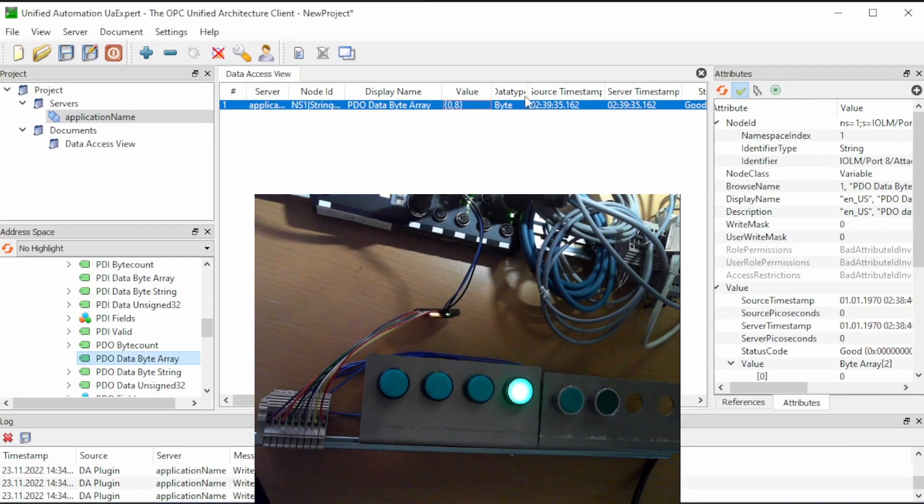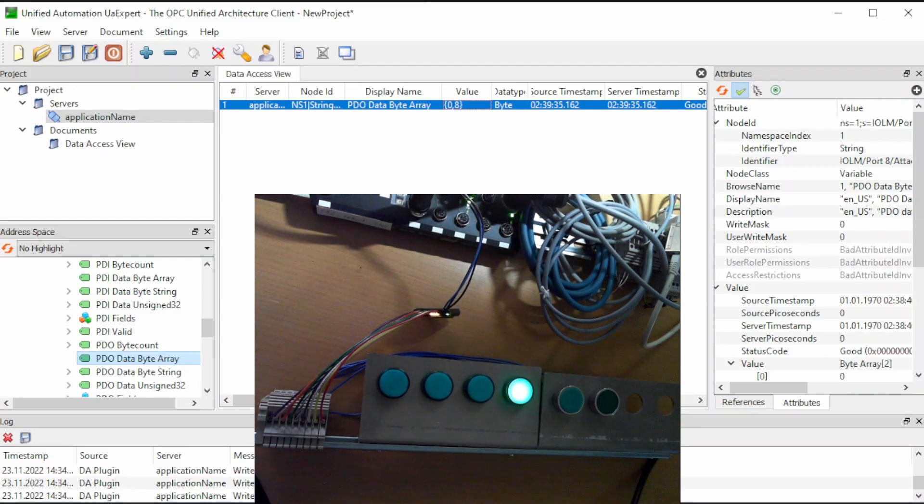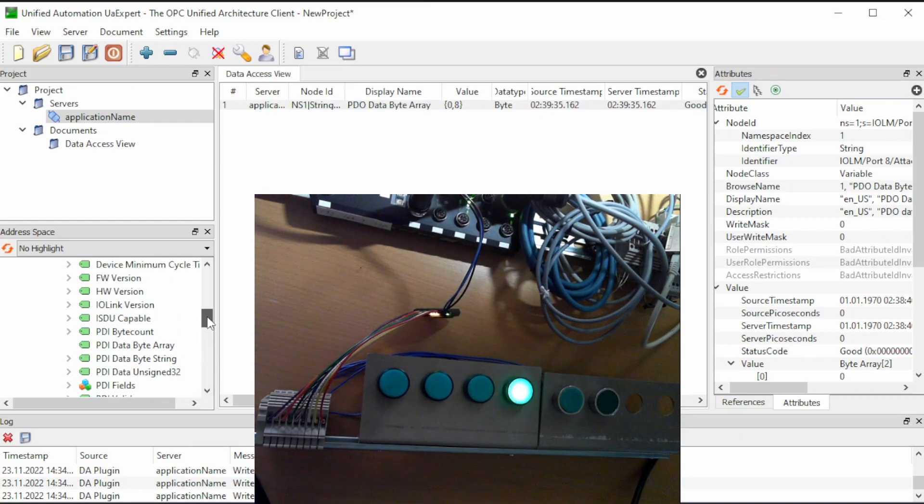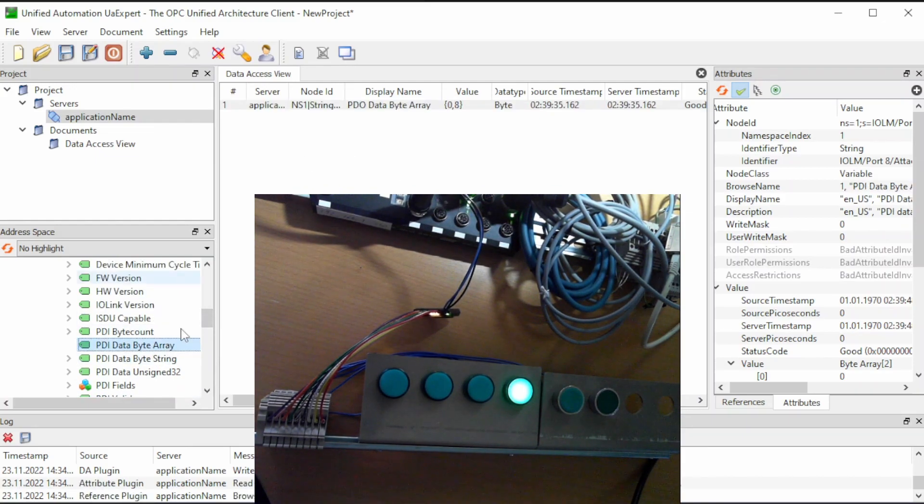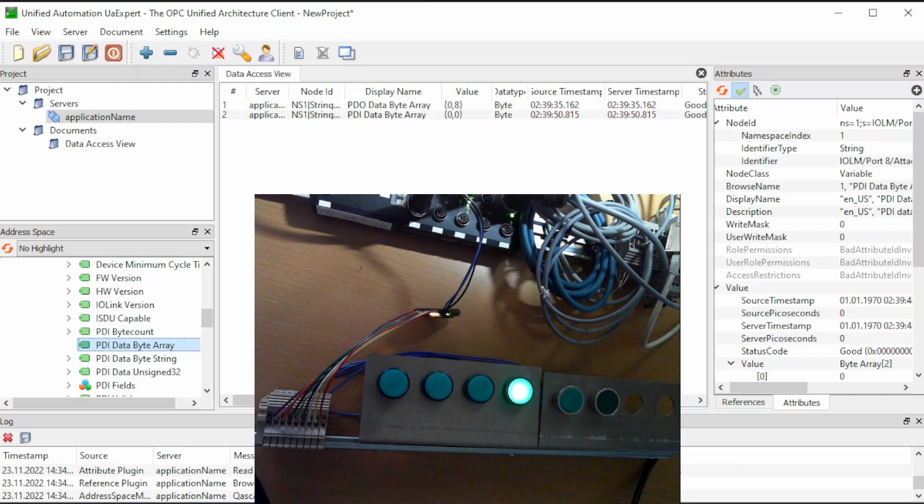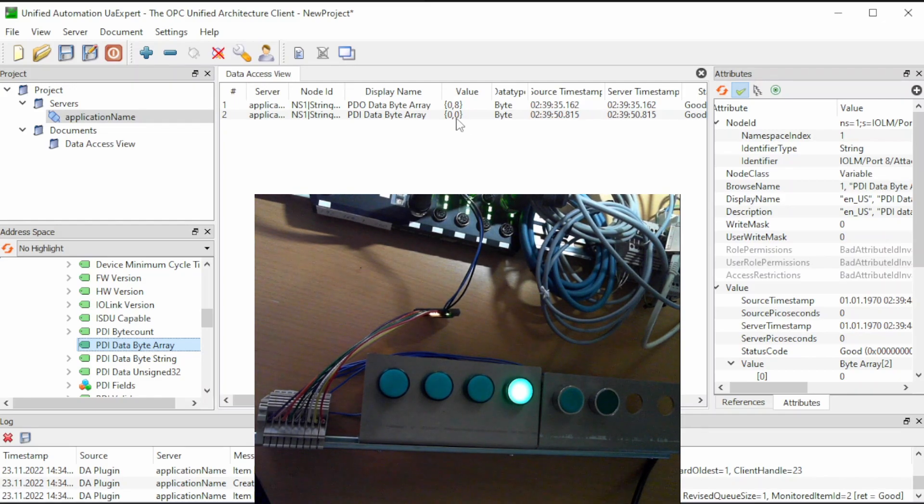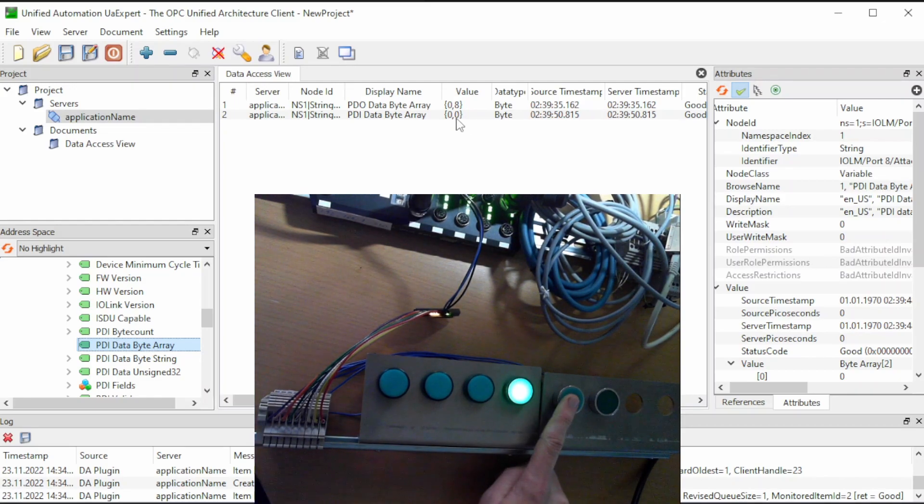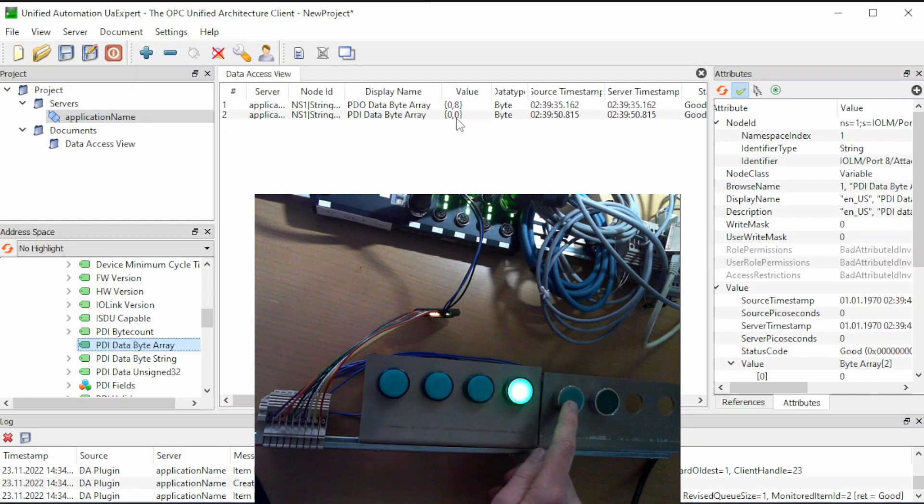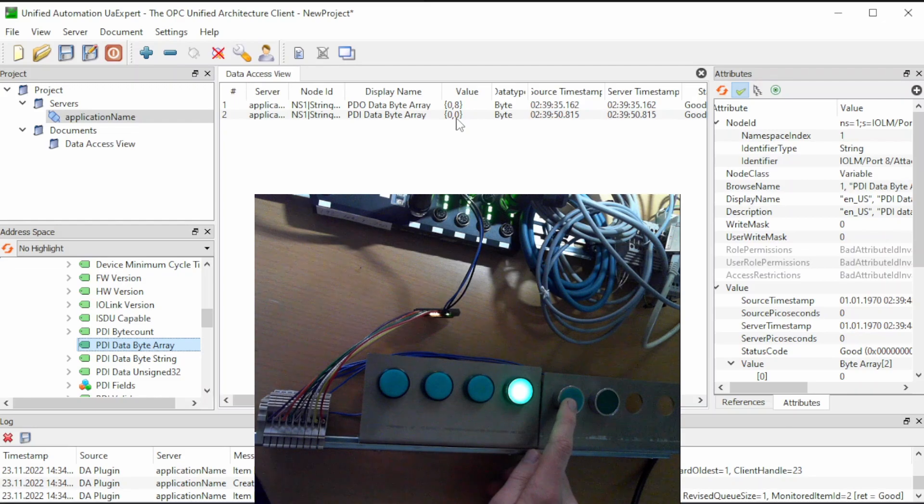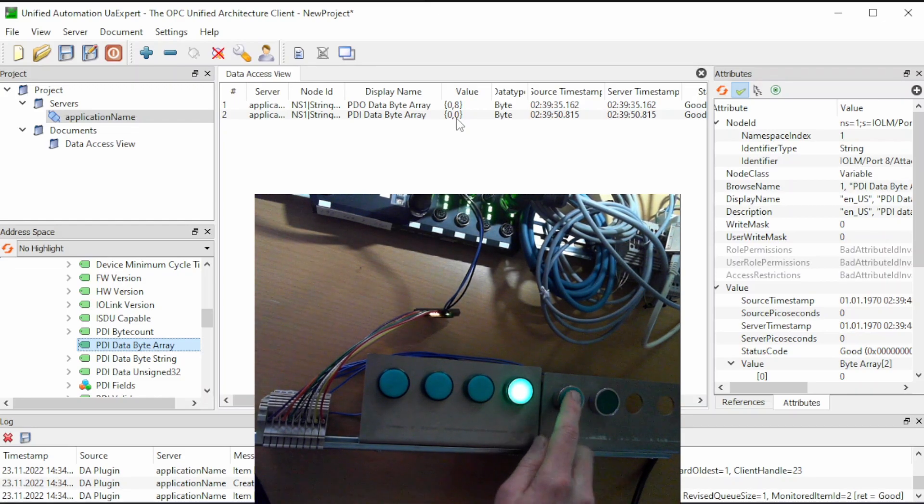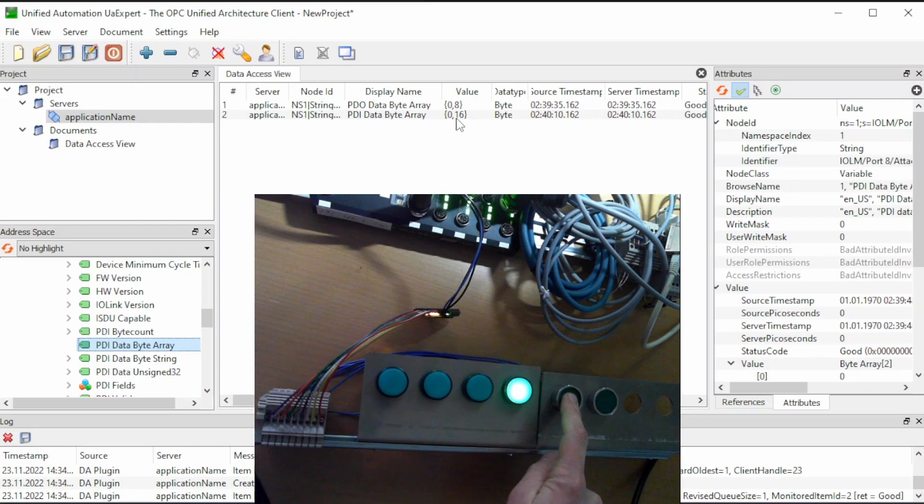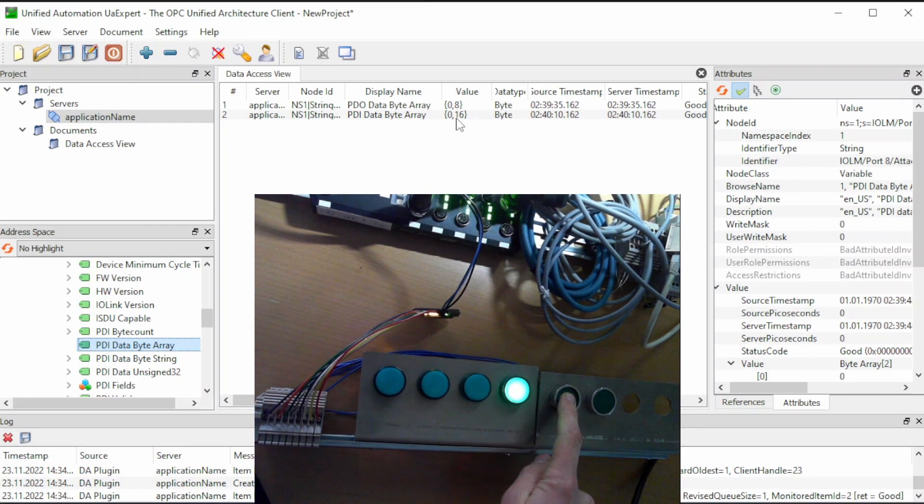So this was the outputs. Then we can go over to the input signals. That is the PDI byte that we see here. And we see that the values are initially 0, 0, but if I press the button here, which is number 5, acts as bit number 5 in the byte, we should see a value of 16 that appears. And when I press it, you see immediately that we get number 16.